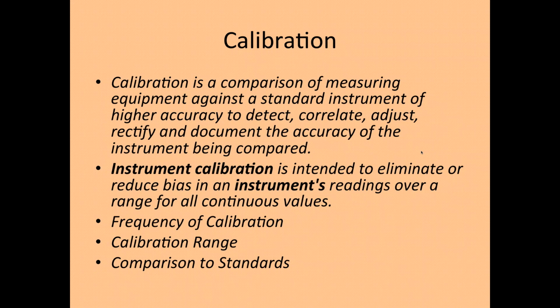How often do you calibrate? That's up to you. It depends on the use of the equipment. How often do you use it, and what are the chances that it goes out of calibration? If you're using, for instance, a scale, you can have a weight, or 2 weights actually. You want to have the high range and the low range, and measure that to see how accurate your machine is. And if it's outside of calibration, you need to bring somebody in, but you do need to have a document on a specification on how often you calibrate for every piece of equipment that you use in the process, either to control quality or to measure quality.